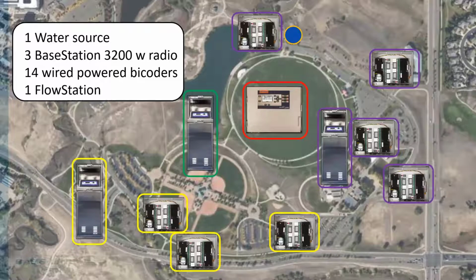That yellow grouping, the yellow controller with the yellow powered biCoders, is connected via a 2-wire path. That's how they're bringing that conventional wire back into the Base Station 3200 and communicating amongst them back and forth, because the 2-wire path carries both the power for the zones and the communication wire for our controller.